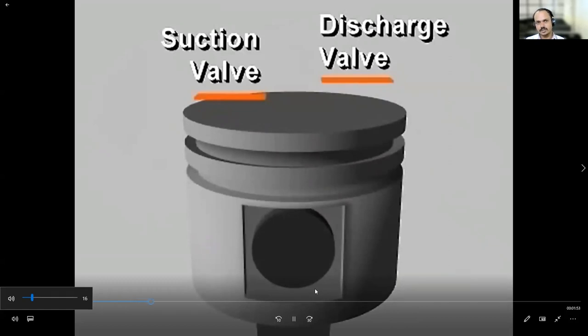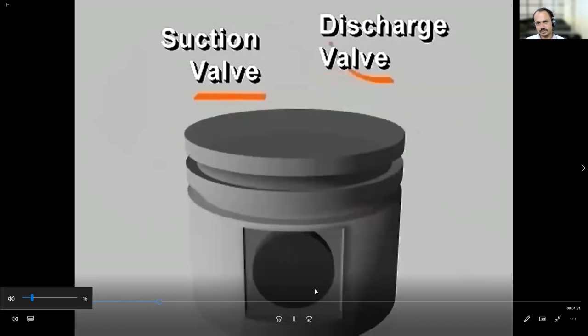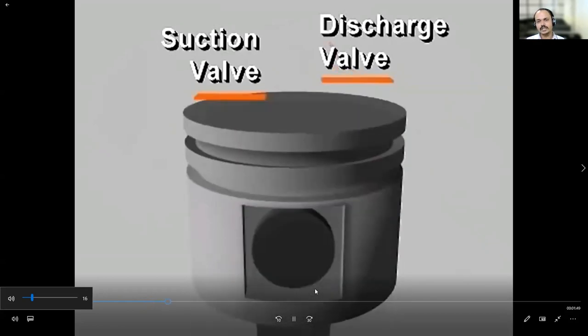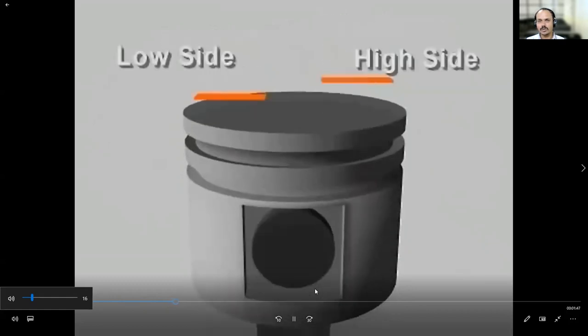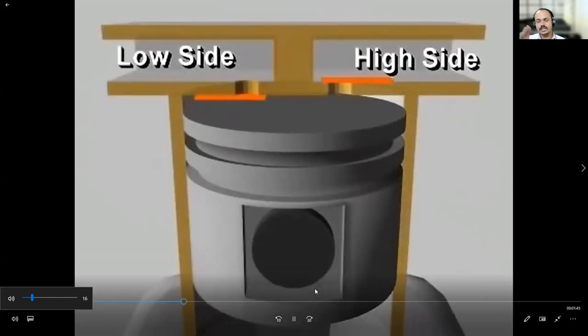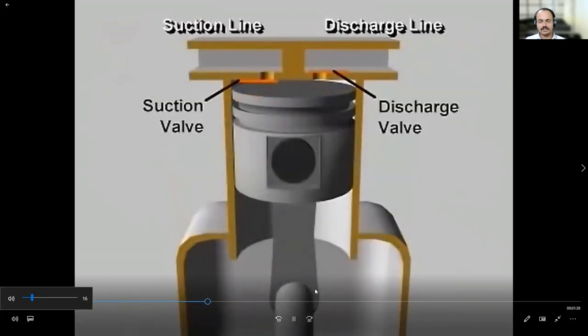So there are two valves, the suction valve and the discharge valve. When the pistons start moving in the downward direction, the suction valve gets open, and when pistons start moving in the upward direction, the delivery valve gets open. So the low pressure side is the atmospheric pressure side, and the high pressure side is the pressurized air side.